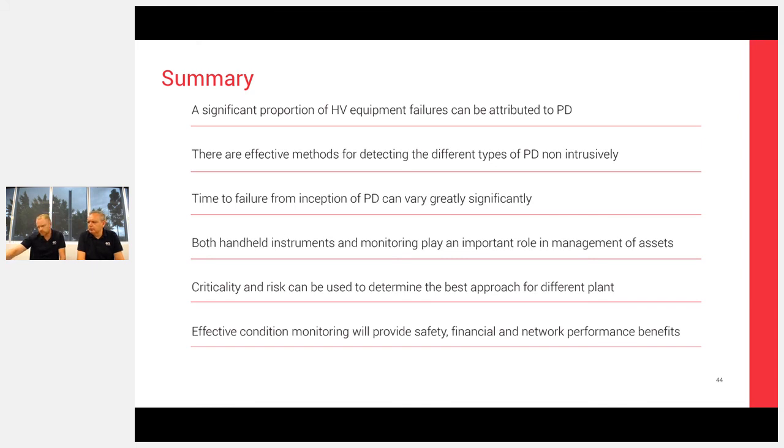Does one node support one RFCT? On the particular nodes that you saw in the pictures, where you've got two TEV sensors and two ultrasonic, that particular node supports one RFCT. We've also got another node, a standalone cable node, which will support 3 RFCTs. So you can have a combination of those in the chain, so you can make sure that you're testing the cables, particularly when you've got multiple cables per phase on some circuits.